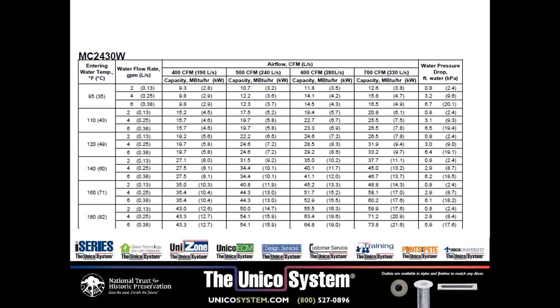When we look at heating with a chilled water coil, now with geothermal, 110-degree water temperature is probably about the most you're going to be able to get out of it. If you have 110-degree water with our 2 to 2.5-ton system, with 600 CFM of air and 4 gallons per minute, we will put out 23,000 BTUs. Now, if we can raise that to 140 degrees, such as working with a boiler, our output almost doubles. The same exact setup will give us 41,000 BTUs. So as I say, the warmer the entering water temperature, the more BTUs we get out of the system. However, to protect the motor that we have, whether it's a PSC motor or an EC motor, it is in the airstream. So we try not to use entering water hotter than 150 degrees.